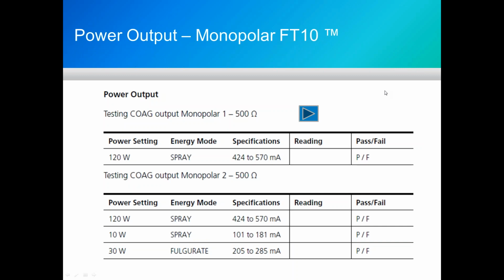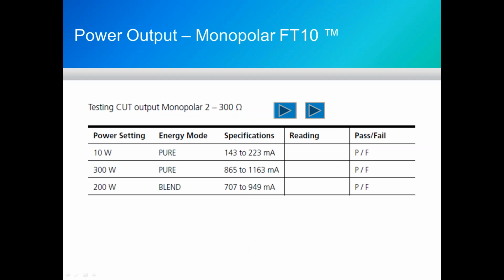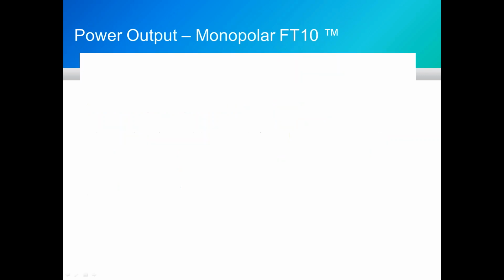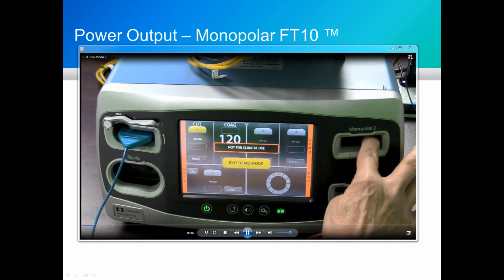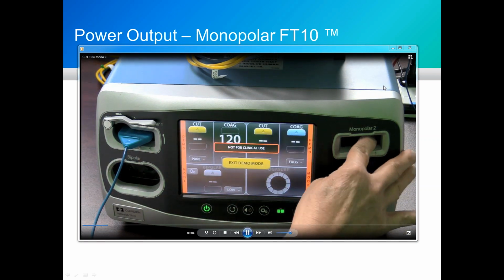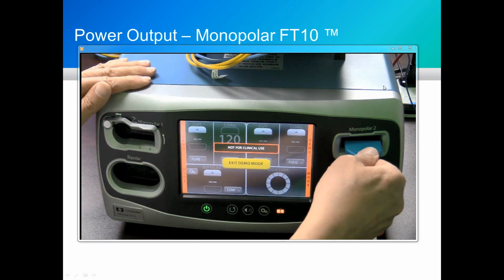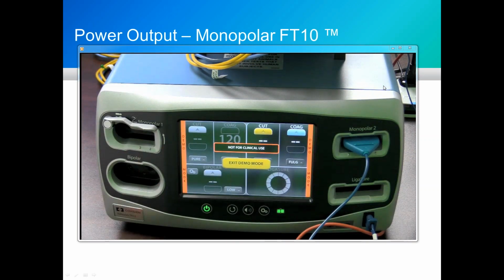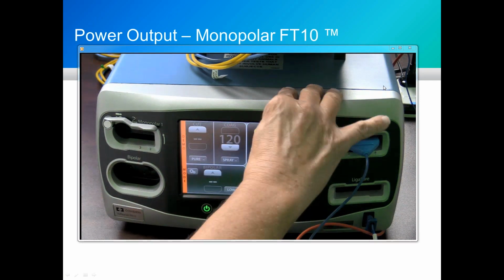So that was a test on Monopolar 1 for Coag. Monopolar 1 is now done. That's pretty sweet. Now we're going to switch over to Monopolar 2, and we're going to do a couple of tests here. Notice there's a little micro switch in that energy output port. So a test pencil helps greatly because you don't want to be pushing that button while you're trying to measure energy. You're too close to the action.